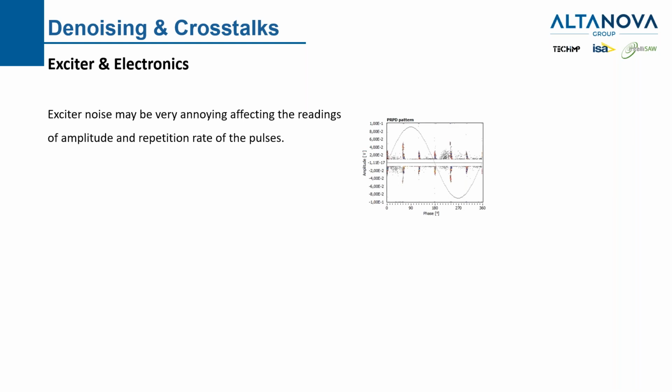A very classical noise during acquisition is the exciter noise. If you see the pattern here, we have a group of 6 vertical lines, very, very stable and very, very precise. Those are basically covering something else. They are mixed with something else. I can say at first sight that it is an exciter noise, and I guess you can see as well the characteristic vertical lines.